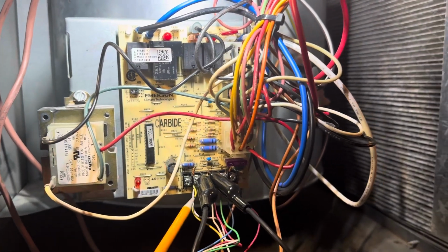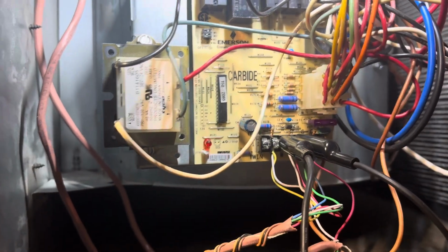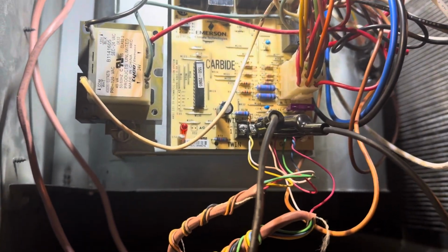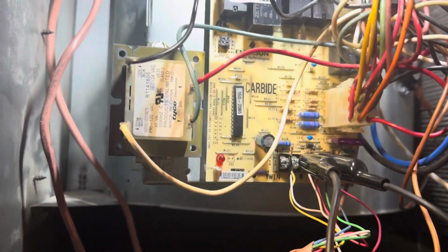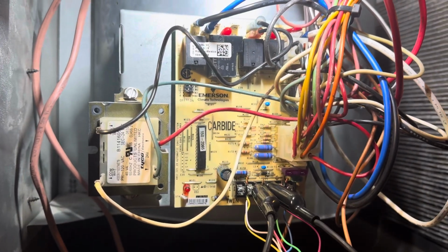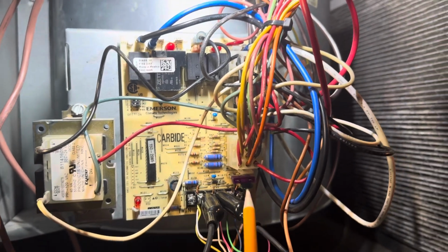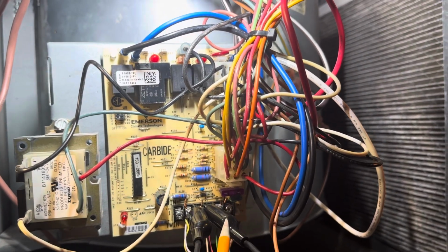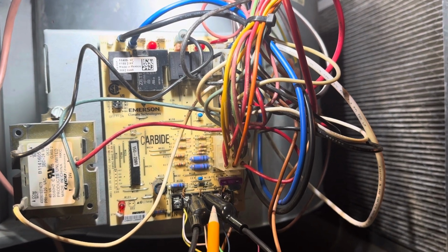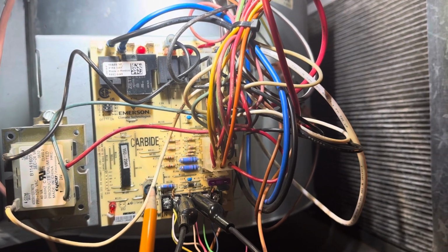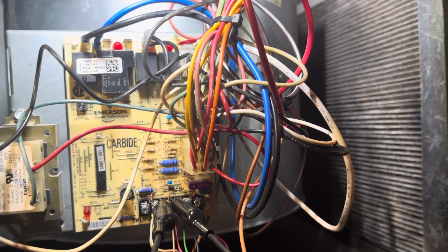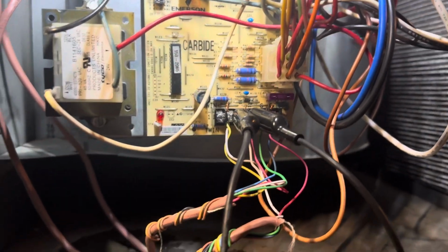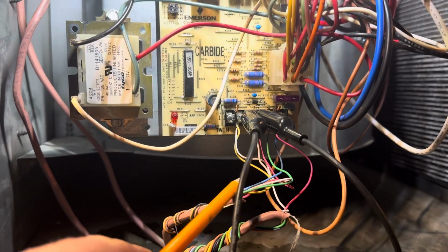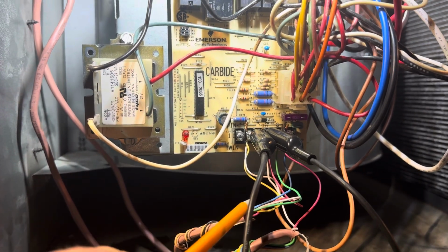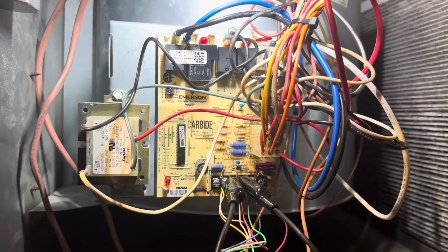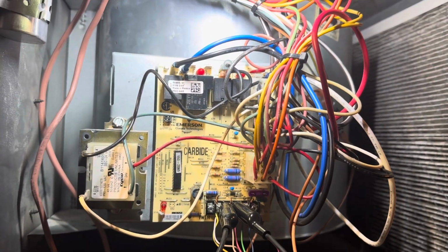So the circuit board, if you look down here, there are terminals, and there's five of them: common, green, red, white, and yellow. And for the purposes of this video, what I've done is I've jumpered red and white. So red is power, 24 volts, and it comes actually off of this transformer right here. And white is heat. So this control board is wired directly to the thermostat. So it's actually the thermostat that does what is called in the industry a call for heat.